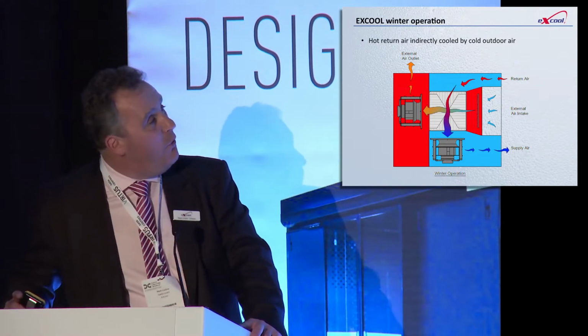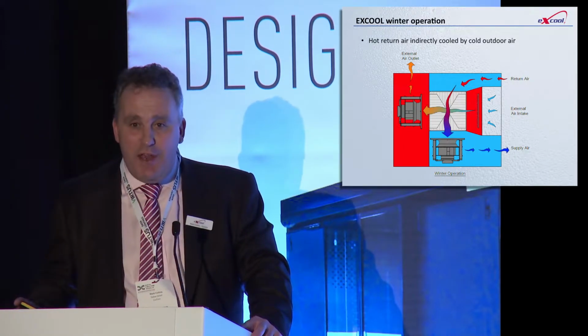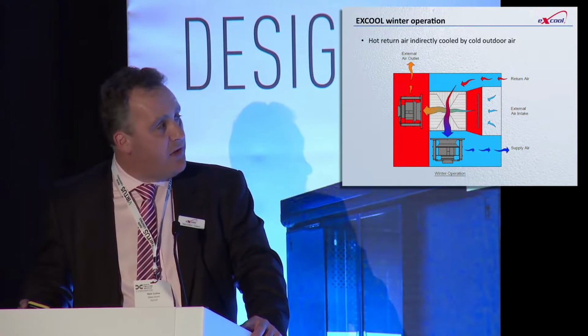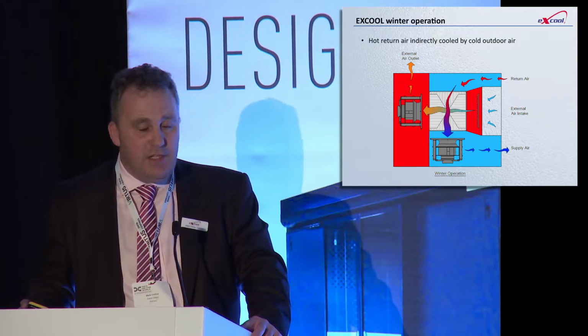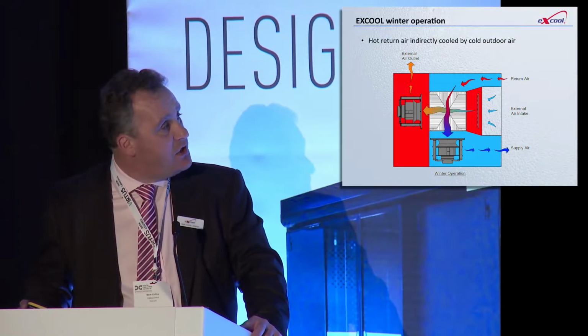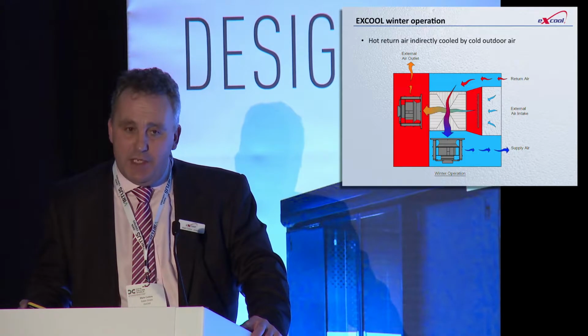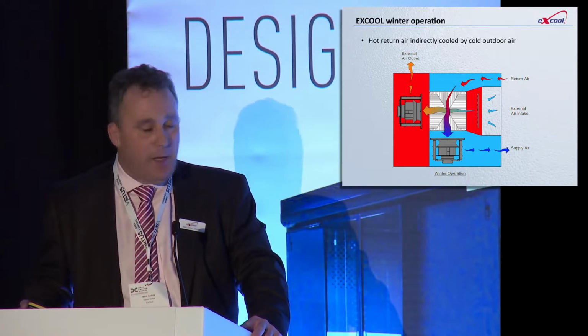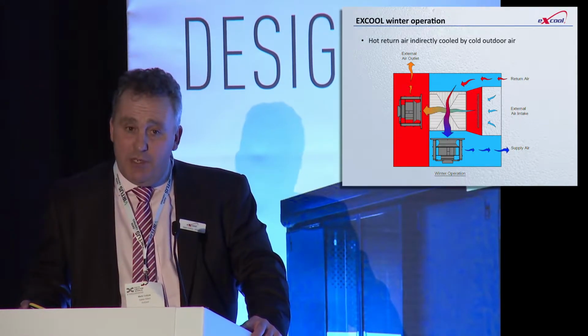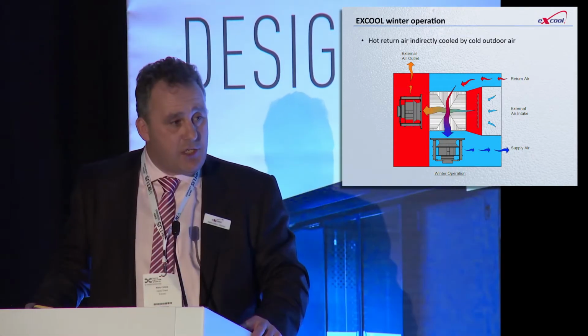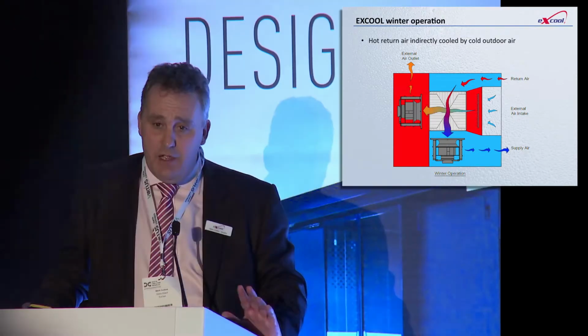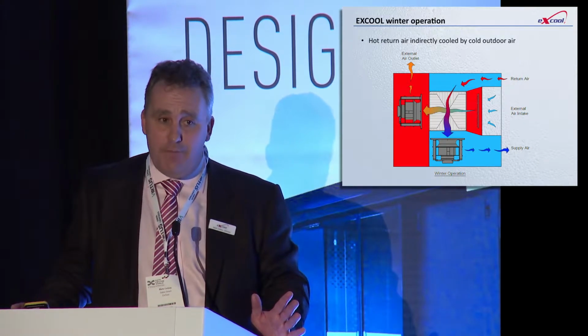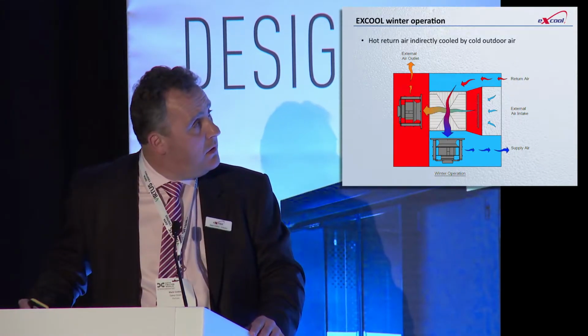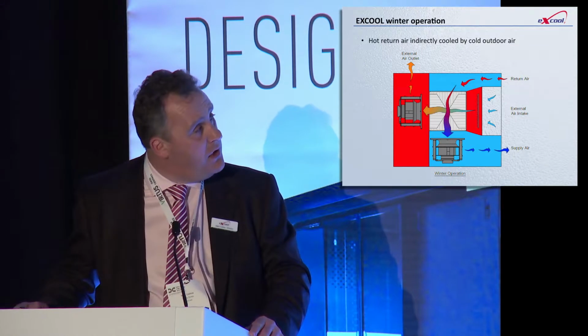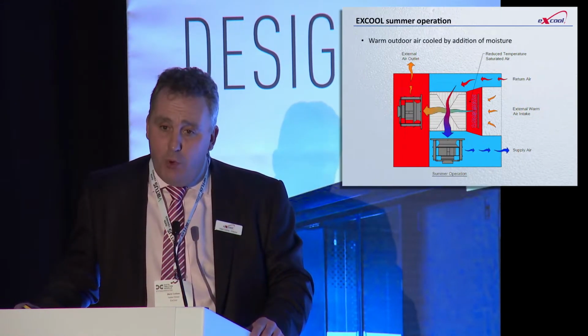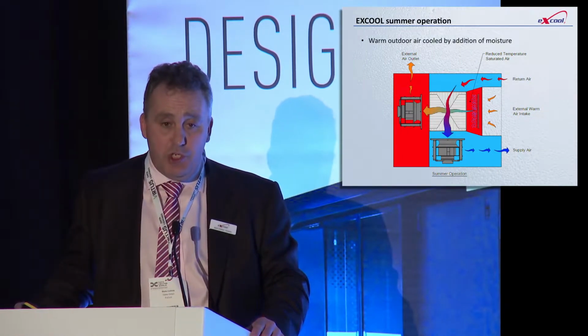I haven't got a pointer, unfortunately, so you'll have to bear with me, but we're taking return air back from the space. We're passing it through one side of a heat exchanger and delivering it back into the space. The external air is being drawn through the other side of the heat exchanger and then discharged to atmosphere. So the heat is basically being removed from the data center and discharged to atmosphere via a heat exchanger. And that is the only heat transfer that we have in the entire system. Okay, and that's winter operation. In summer, we add moisture to the outdoor airstream to reduce that temperature down.